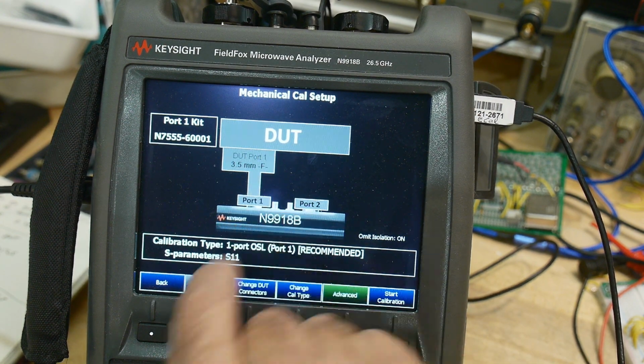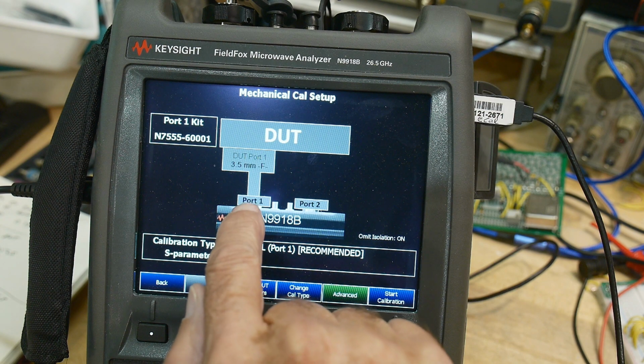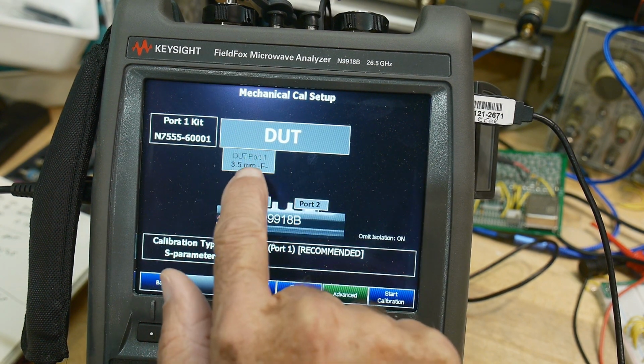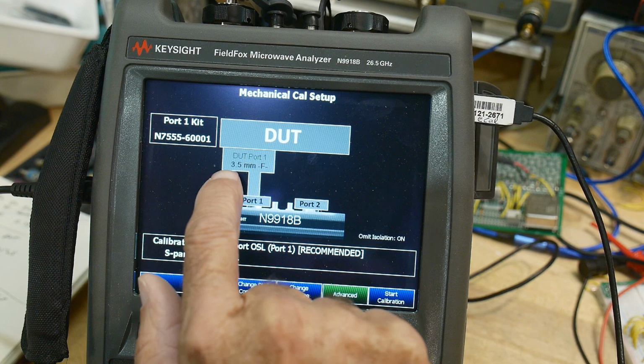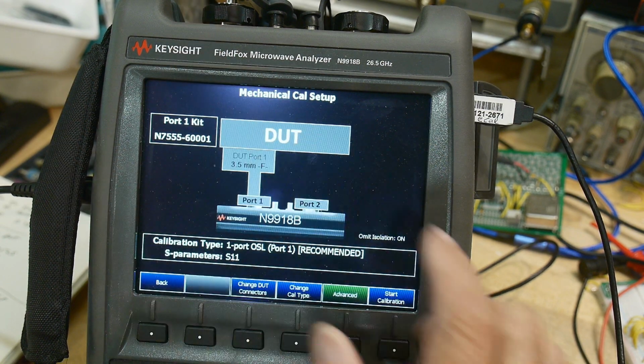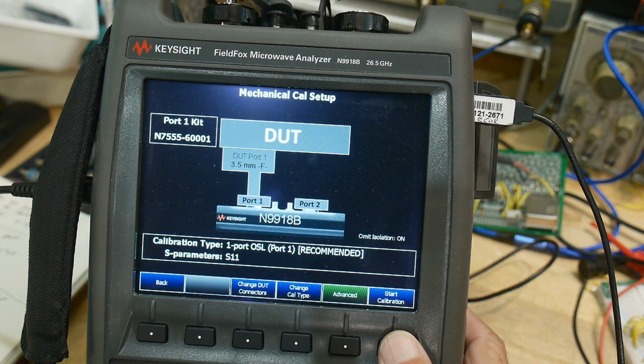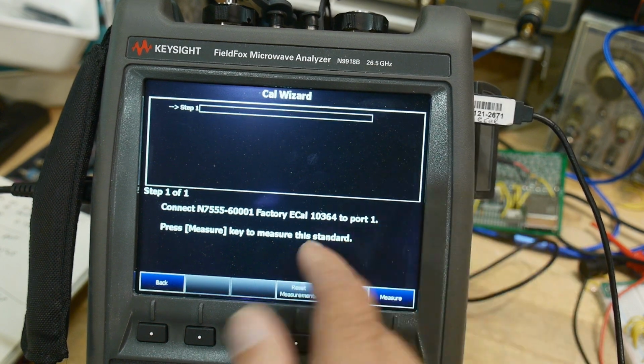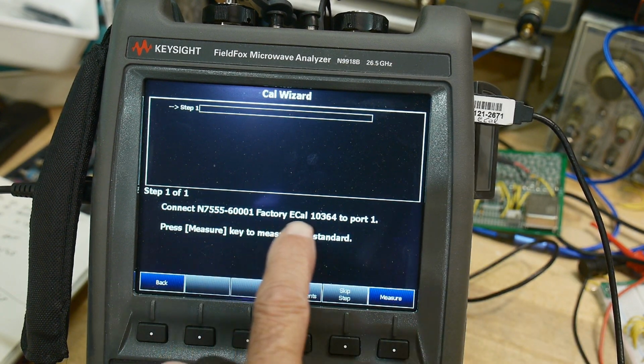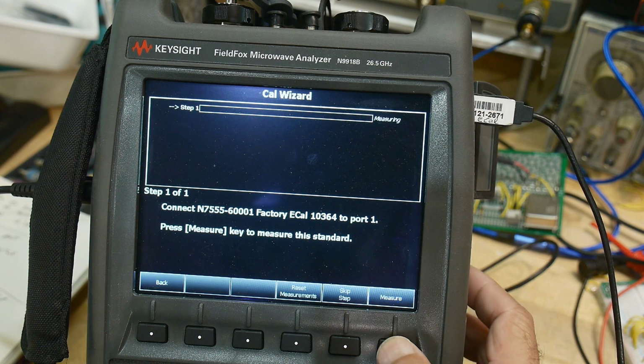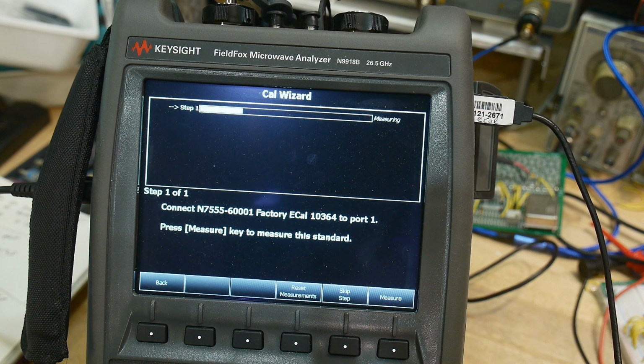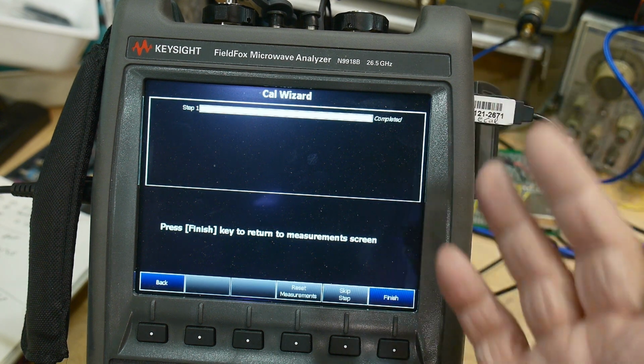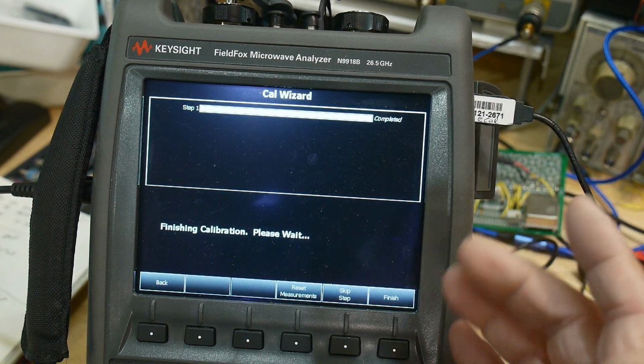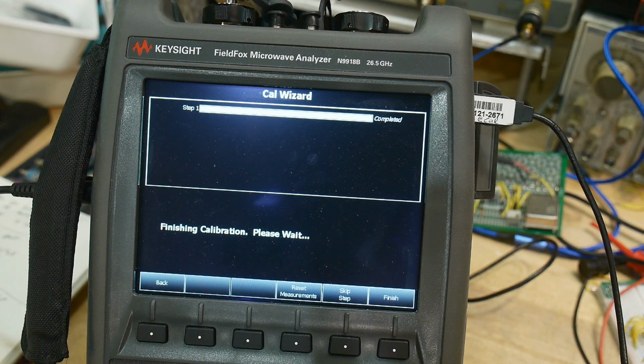and then it tells you how to hook it up. So it says, okay, you're going to be doing S11, so you need to hook it up to port 1. You need to hook it up like this. You've got a 3.5 millimeter female connector on the eCAL. Yeah, everything looks good. You hit start calibration. It says connect the eCAL to port 1, and then press measure. And it's done the open short load all in one pass. So we are now calibrated. We are now ready to go.